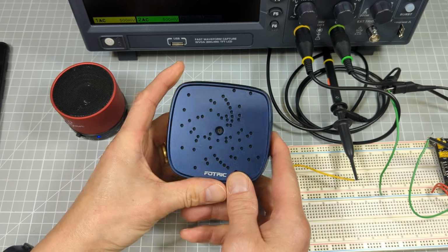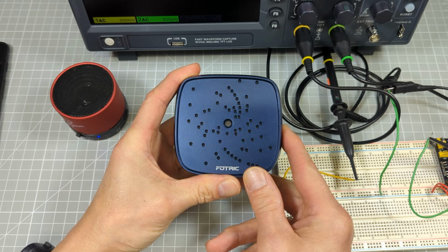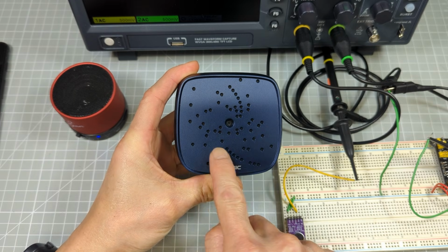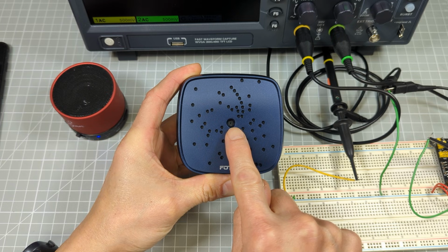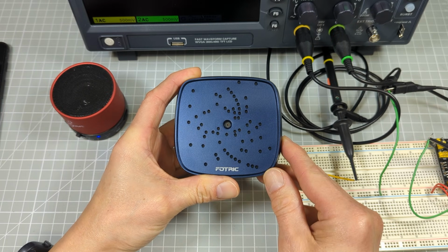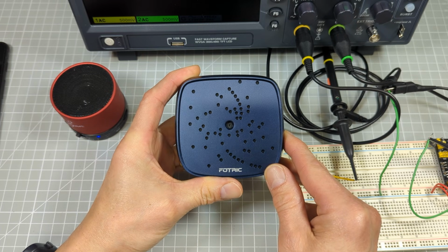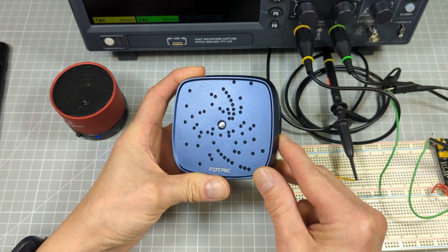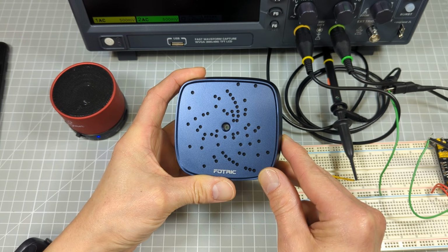So the Fotric sensor takes this phase difference comparison to another level. It uses 64 microphones, which are the smaller holes on the front of the sensor. The larger hole in the centre then is a normal light camera, which it uses then to show the scene we're looking at. So the data from each of these 64 microphones is then processed to separate the individual sounds, and then these sounds are compared across the whole microphone array.